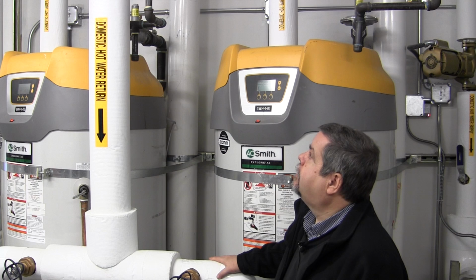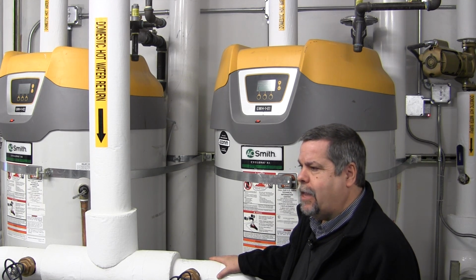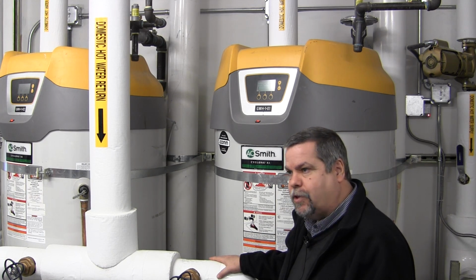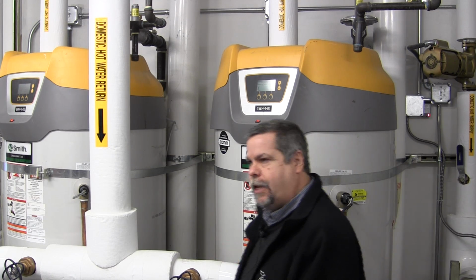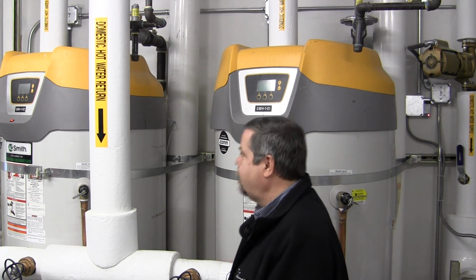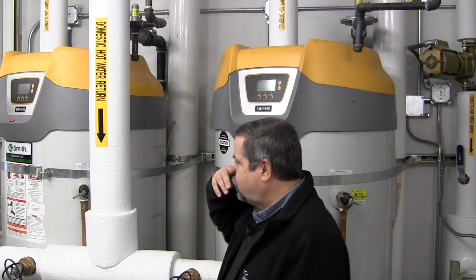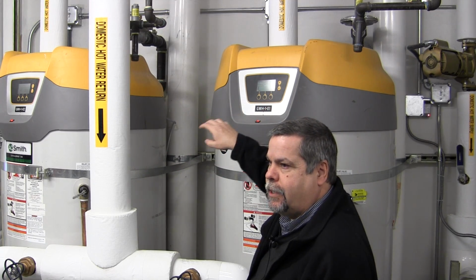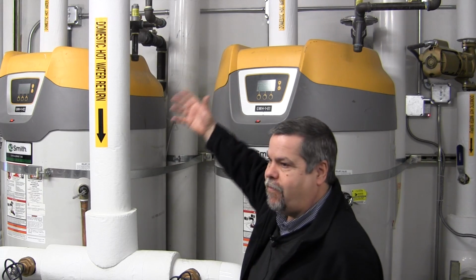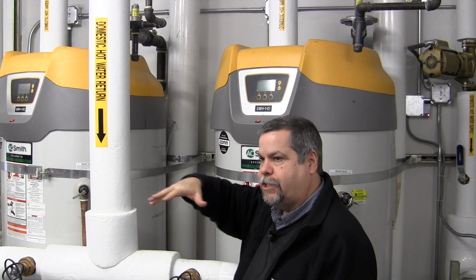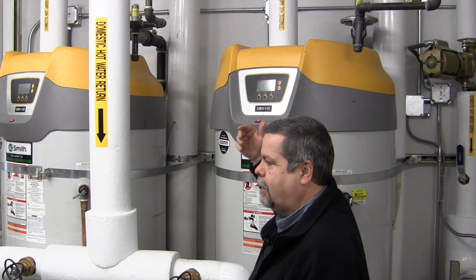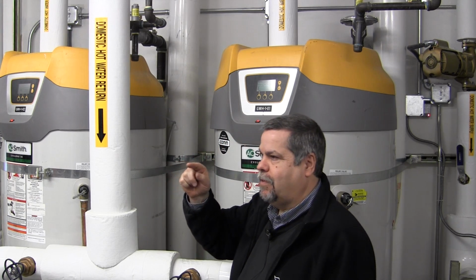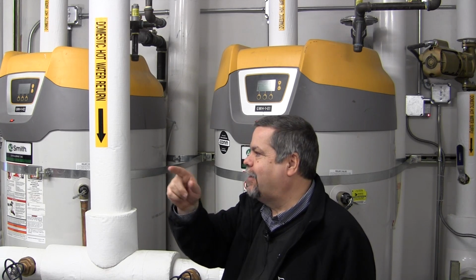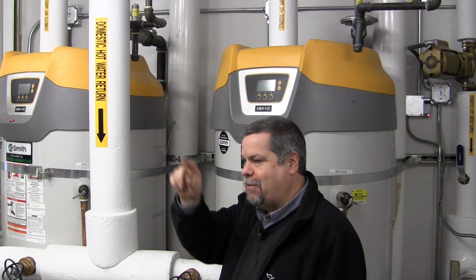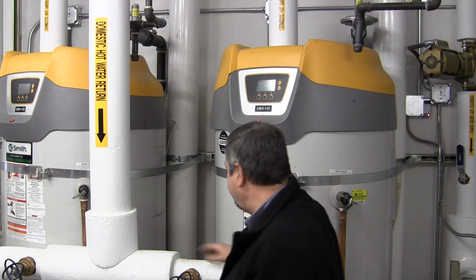I'm sure you guys are accustomed to. In your O&Ms are step-by-step procedures on cleaning and flushing, unliming, checking the T&P. There's a troubleshooting guide that explains the error codes. There's a section on how to program. If anyone wants to get up here and play with the control, I encourage it. It's fairly simple. The difficulty comes in is you're in a menu and you want to get out of it. Do you push update or back, but it's not. So you might hit the wrong button a couple times, but you figure it out pretty quick.